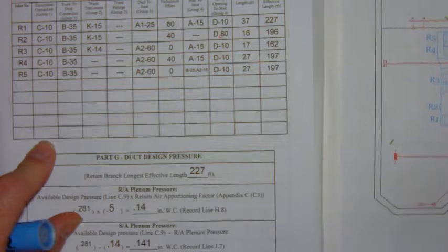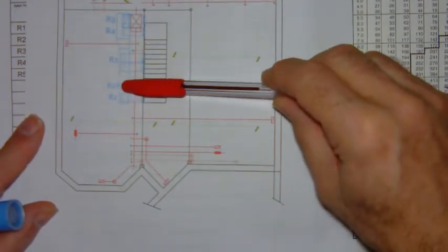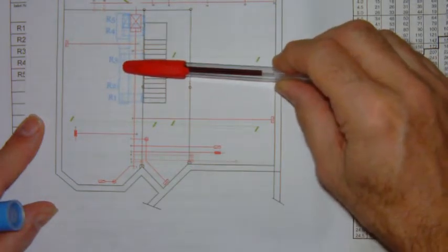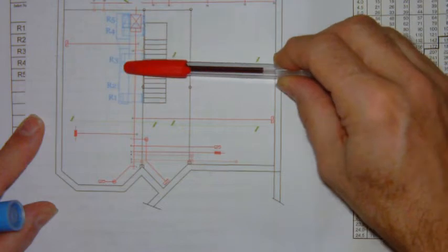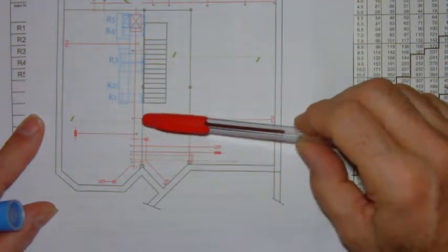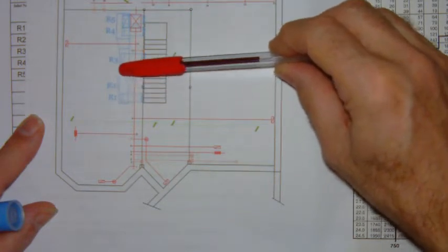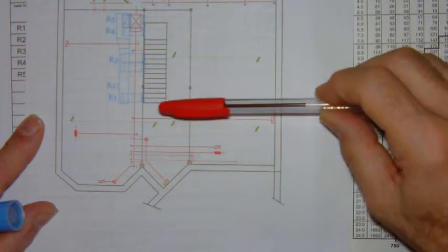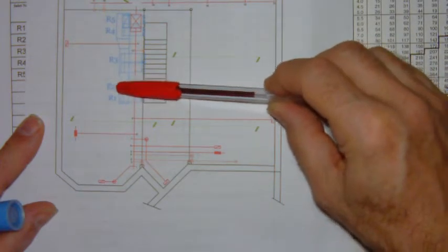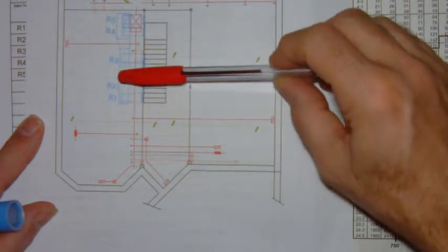Now the turbulence, if you recall, turbulence is the idea that as the air from R2 travels back towards the furnace, it bumps into or intersects with the air coming from R3. So this creates turbulence, congestion, if you will. Every time a return air bumps into an adjacent return air, you have to add 40 feet for the equivalent length. So for R2, you would add 1 times 40 because of R3.